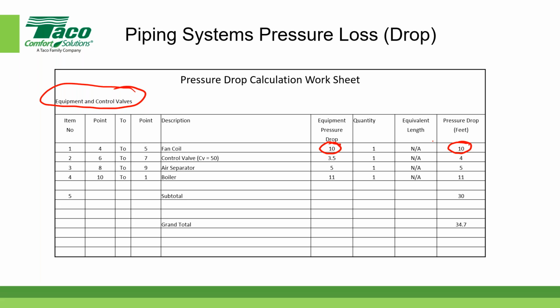So in this particular case, I had to go to the manufacturer's data, and for this particular fan coil that I selected with a flow of around 61.5 gallons per minute, its pressure drop was 10 feet. And that's published data. I can't calculate it. I have to go to the manufacturer and look up that data. Also true of the control valve. We have a control valve in there, and the control valve has a CV of 50.